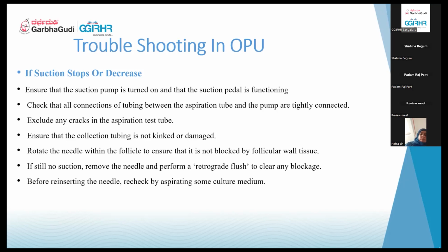The fluid does not get aspirated. When does that happen? When there are any loose connections in between, so there's an air leak happening. Therefore no proper suction is created. So what do you do? You need to check whether the tubings are all connected properly and tightly.